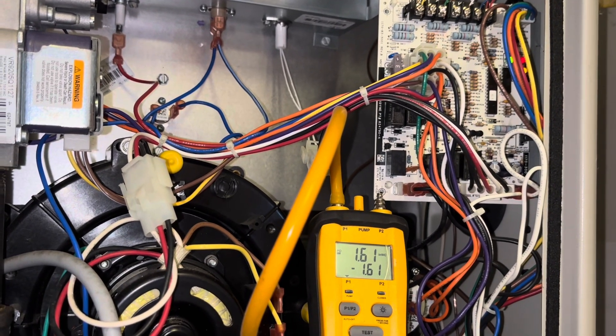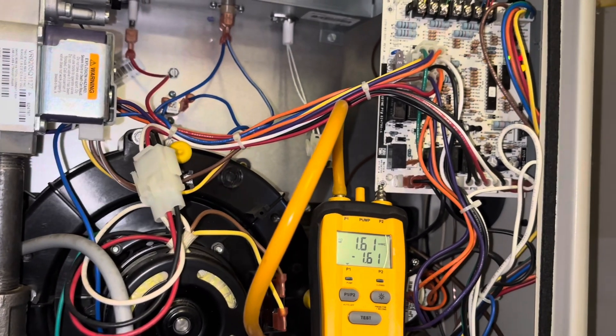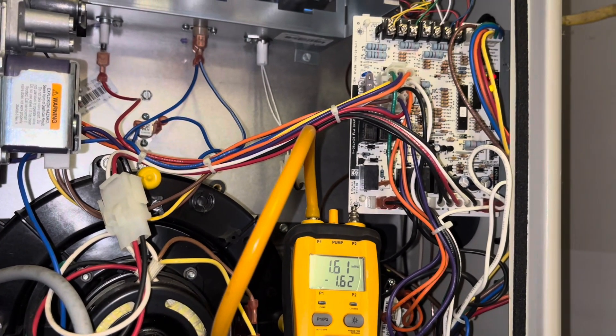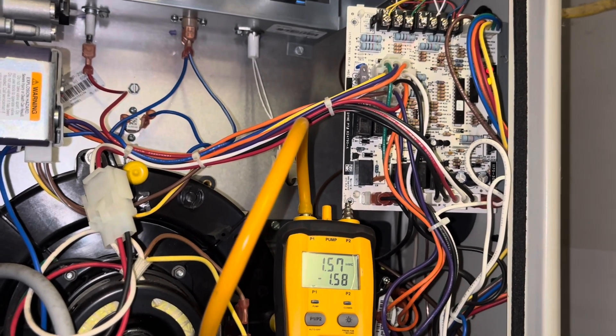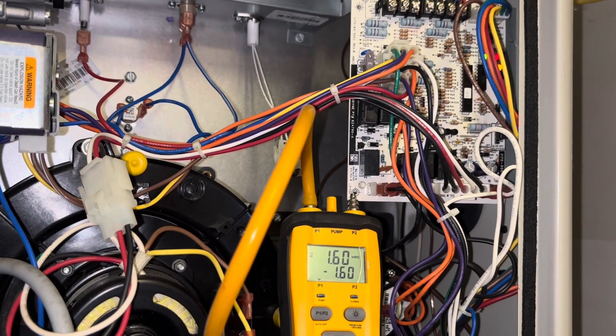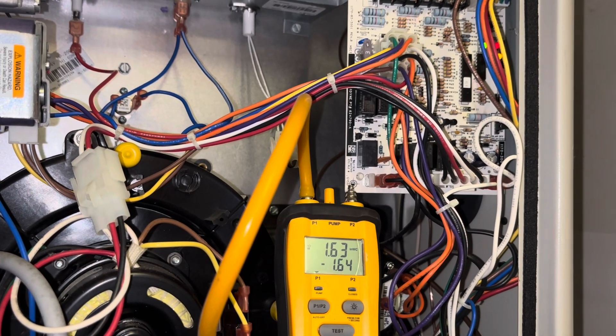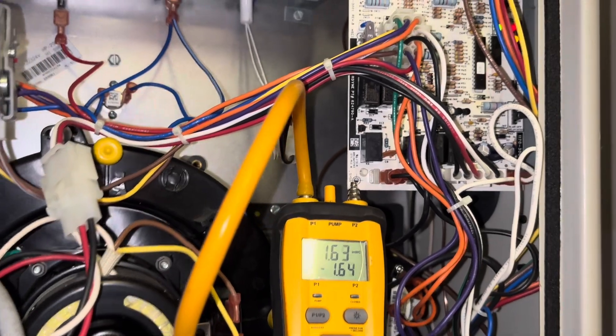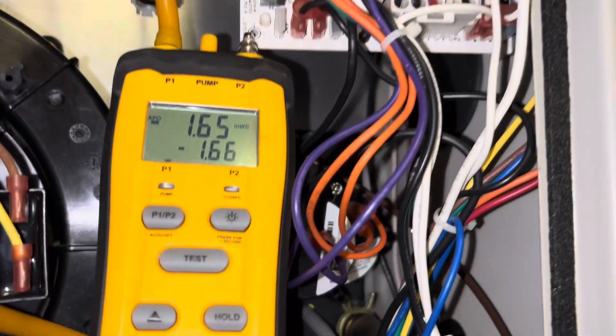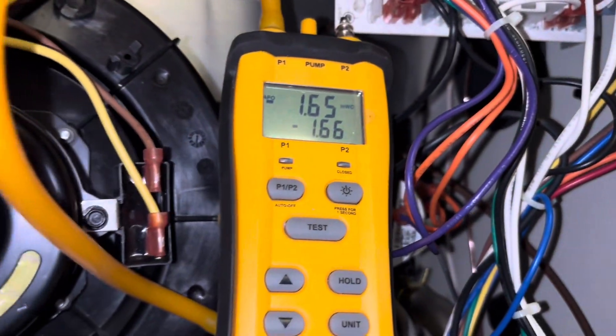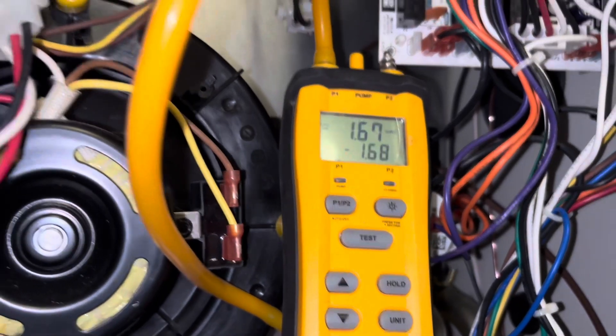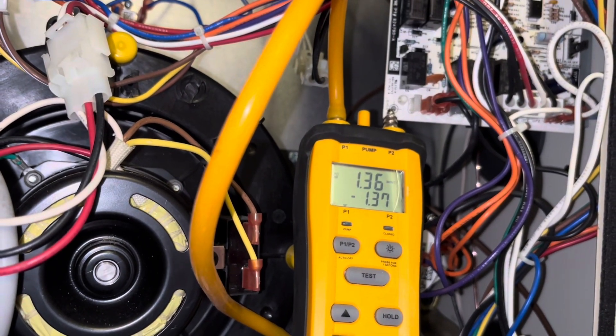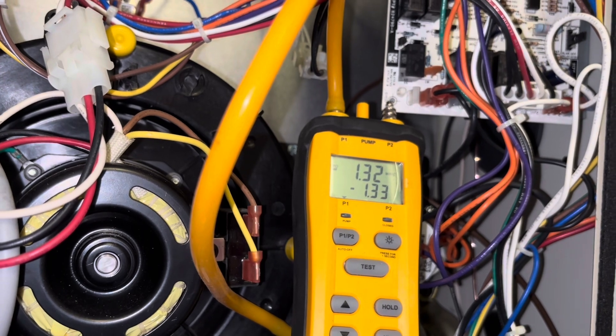The two first stage ones are a 0.7 and a 0.43, and the second stage is a 1.0 and then also a 0.73, I believe. So typically, the pressure switches don't go bad, but on these furnaces, for some reason, they do go bad.